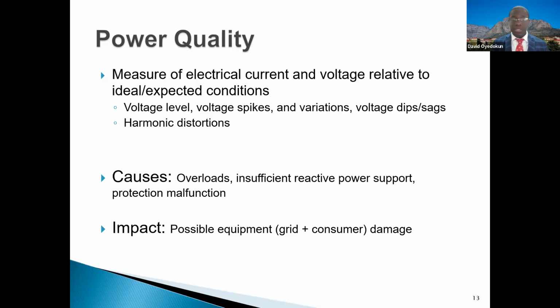The grid code stipulates the maximum level of harmonic distortion allowed to exist in the network at various measurement points, and the lowest dip that should be realized in the network in the event of a contingency. But what leads to power quality issues in general are matters regarding overload, especially at far-flung ends of the network, insufficient reactive power support, and protection malfunctioning.